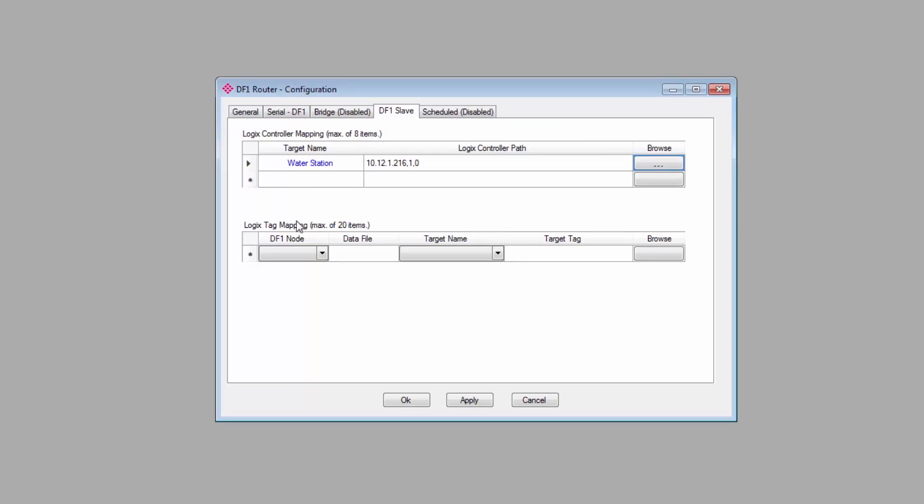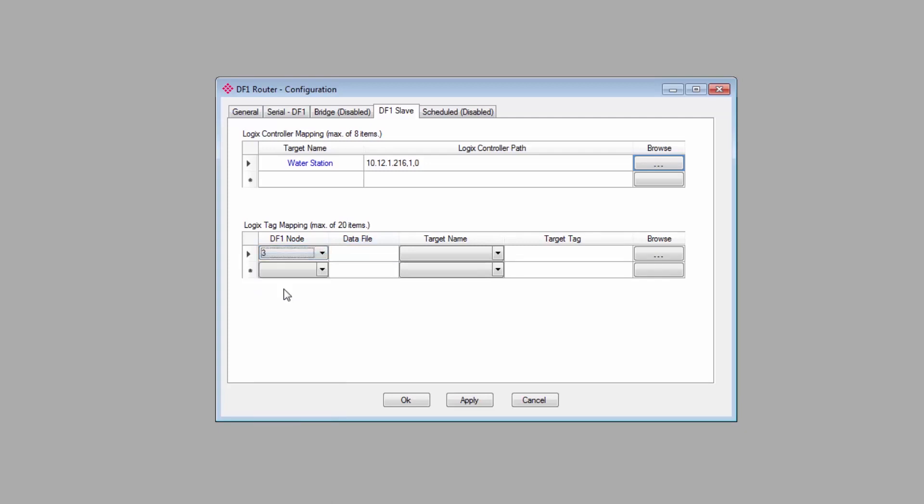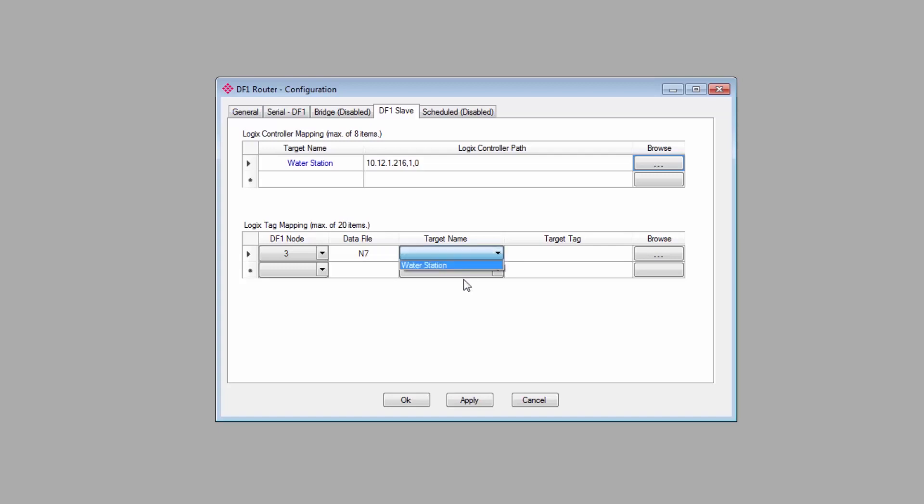At the bottom, under Logix tag mapping, you'll specify the node or nodes the PLX51 should emulate, and the corresponding data files will be mapped to the controller tags. First, enter the DF1 node that the PLX51 will emulate on the network. I've selected node 3. Next, enter the data file that node is expecting to read or write to. For me, it'll be N7.